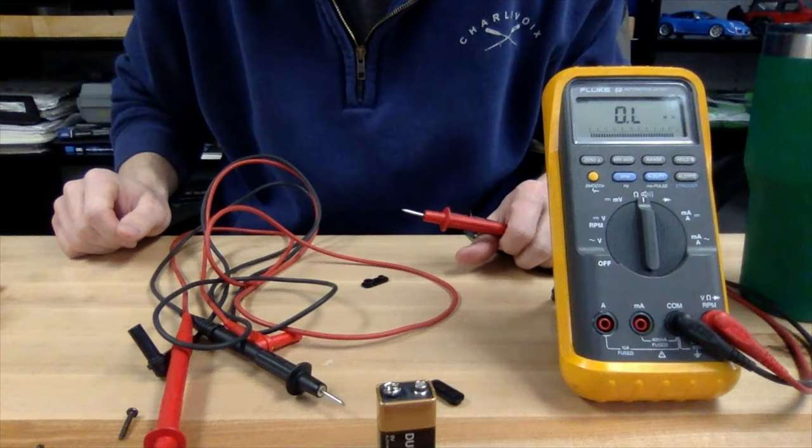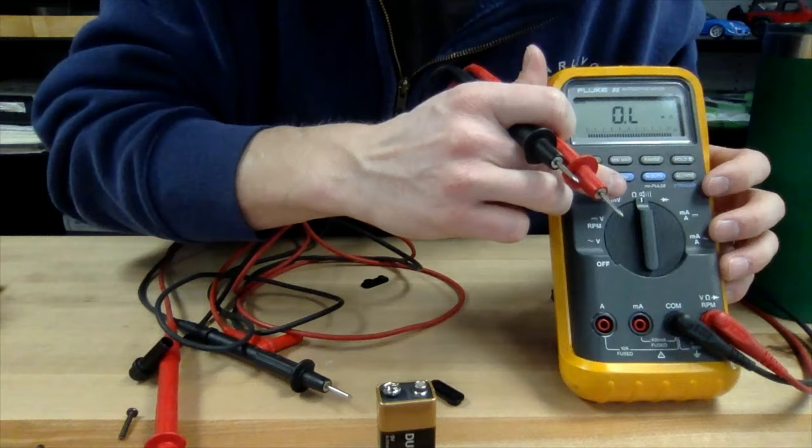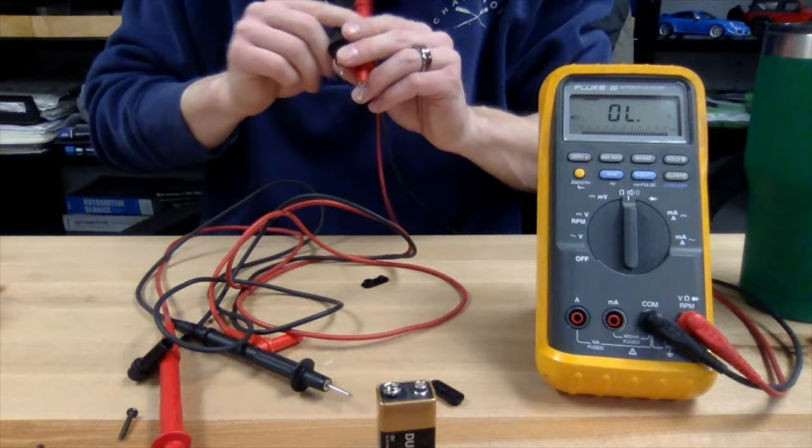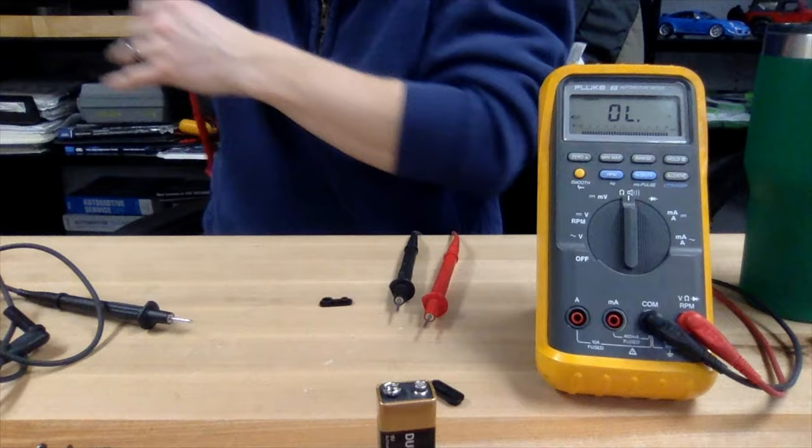So we're going to check out our test leads using the resistance setting or the ohm setting. There's a speaker on that setting, and essentially what I'm doing here is checking for continuity. If there's a complete path from point A to point B, the speaker will beep. We'll check both leads to make sure that both are working properly.